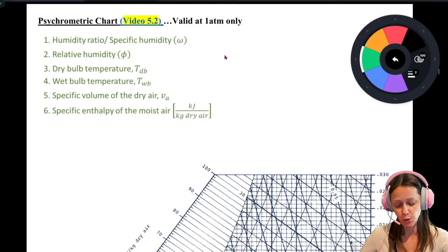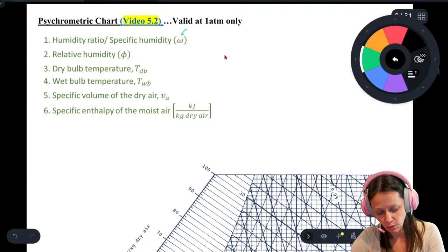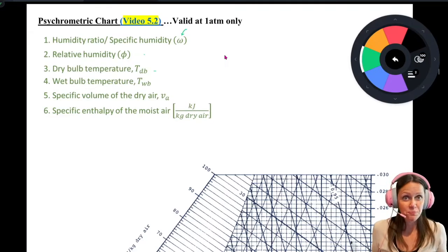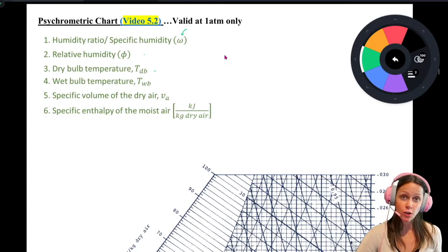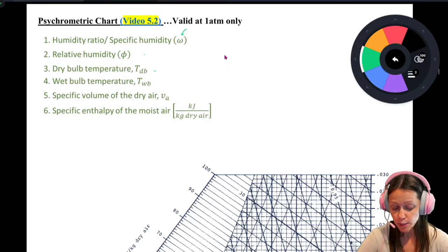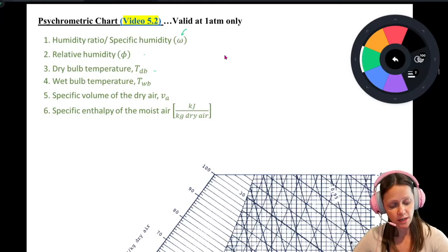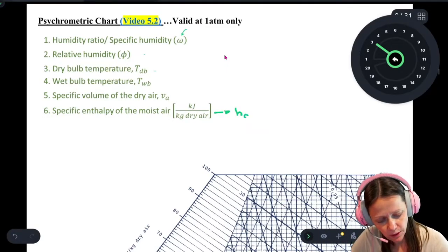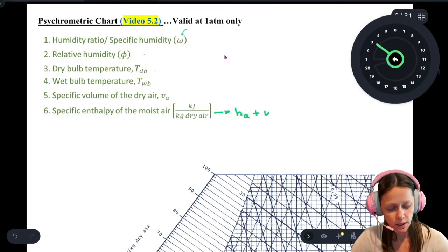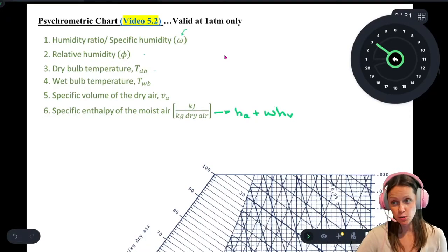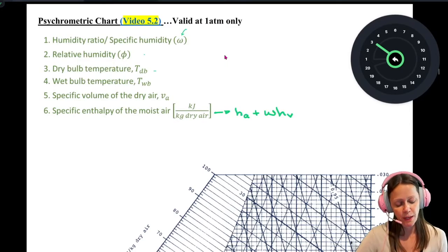From the chart you can get the specific humidity — that's omega — you can get relative humidity, dry bulb temperature (which is just the temperature you think of when you think of temperature), and wet bulb temperature, which is the lowest temperature you can reach by evaporative cooling alone. You can also get specific volume of the dry air and specific enthalpy of the moist air — the enthalpy of the dry air portion plus the specific humidity times the enthalpy of the water vapor.